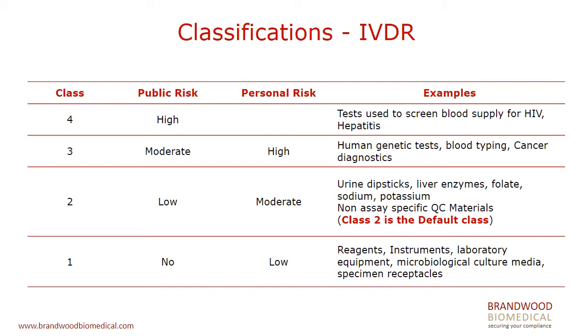So we have a classification system from 1 to 4, and as both the public and personal risk accelerates, you see higher risk classifications. The key thing here is that class 2 is the default, so if a device doesn't fit easily into any of these other classifications, then class 2 becomes the default. At the moment in Europe, very few IVDs are subject to pre-market review or conformity assessment by notified bodies. Under the new classification system, almost all IVDs will be class 2 or higher, so that entire industry is now going to be subject to a technical review at a much higher level.